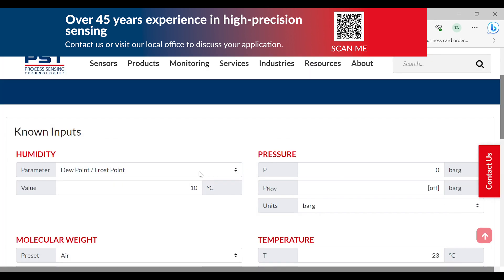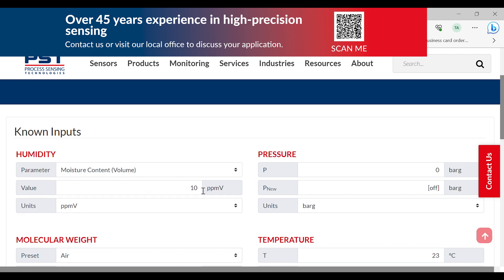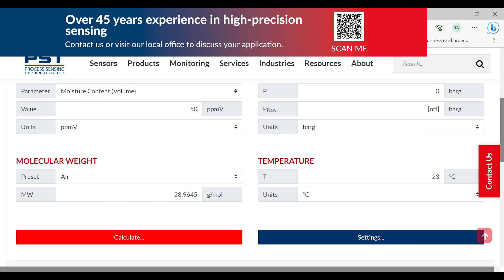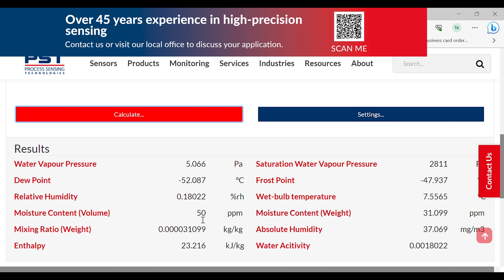As an example of how to use this calculator, I want to find out the equivalent frost point of 50 ppmv. To do this, we select the parameter under humidity, then moisture content by volume, and change the value to 50 ppm in air. Make sure the molecular weight is set to air; for pressure and temperature we don't really mind. We press calculate, scroll down to the bottom, and as we can see, 50 ppmv moisture has an equivalent frost point of minus 47.937.